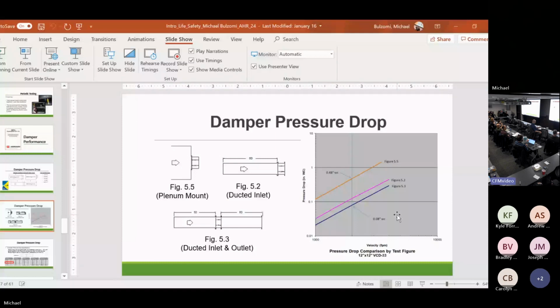So Greenheck and other manufacturers can use variable blade width technology where they have more than one width blade. So if I've got a really tall damper, I can use combinations of 5, 6, and 7-inch blades to make up that space. But some manufacturers have one size blade, 5 inches. So if they have to make up the rest of that space, they just put in a blank plate.